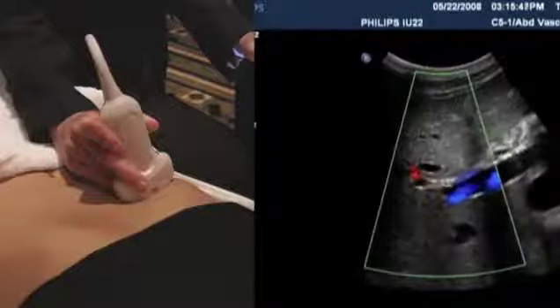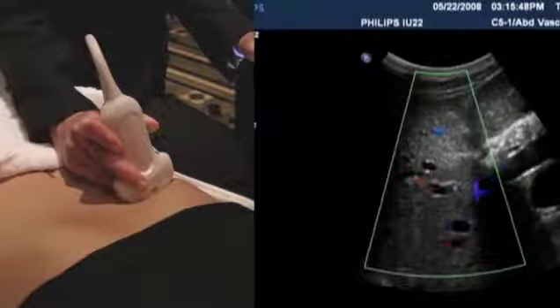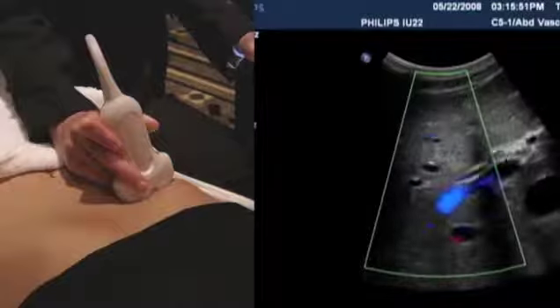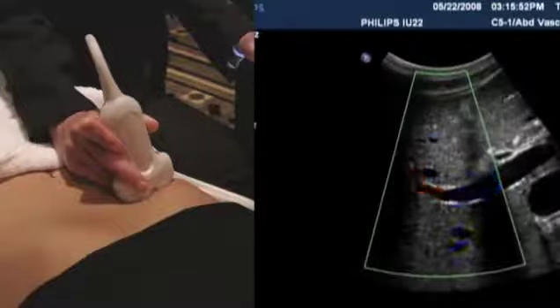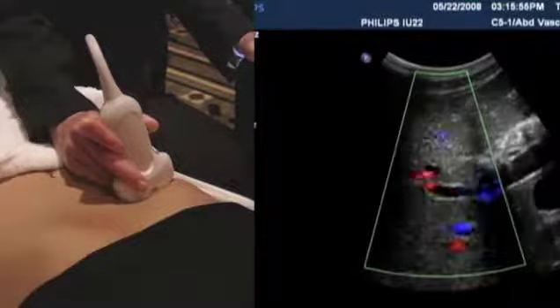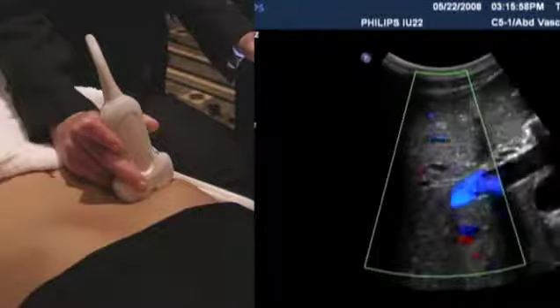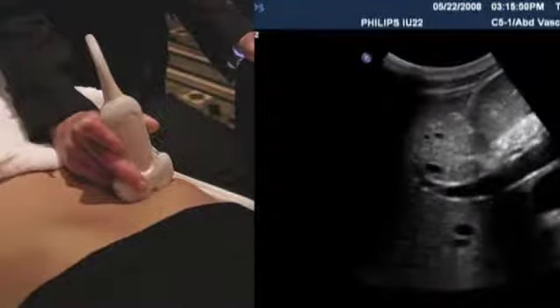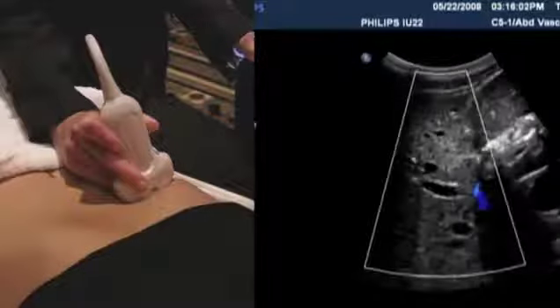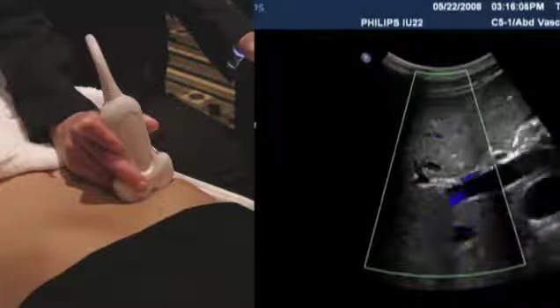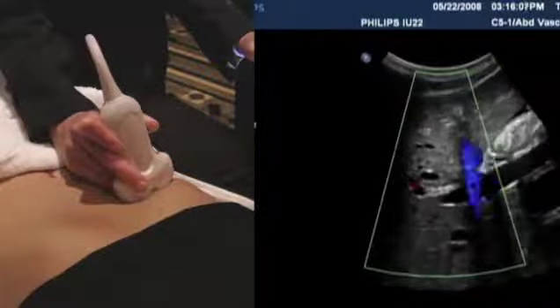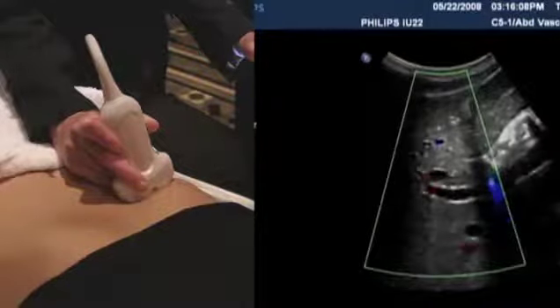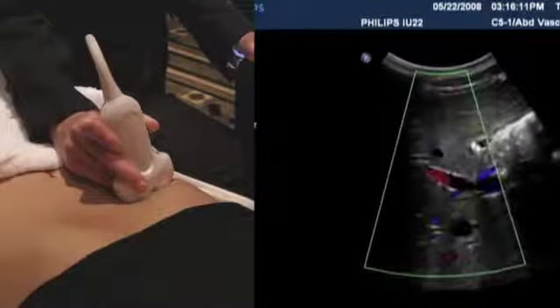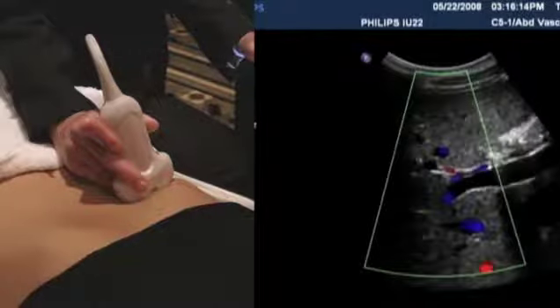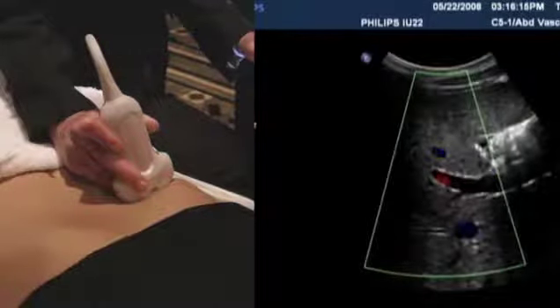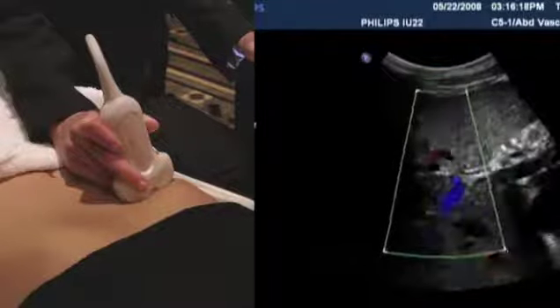And if you don't want to have one of those fancy things, of course, the other thing that you can do is just change the direction that you're imaging, so you are no longer at 90 degrees and therefore are more sensitive. A third thing that you can do is to decrease the size of the color box, because that will also increase your sensitivity to flow. And you also always want to make sure that your depth is just at or just below the level that you are scanning.